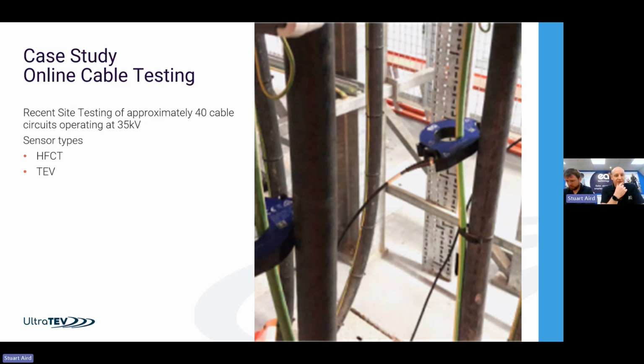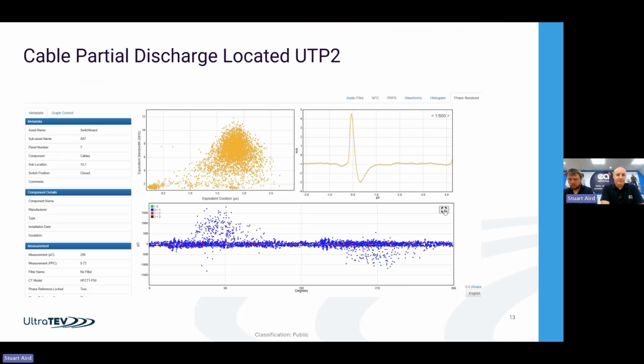A couple of the cables showed some evidence of partial discharge, which I'll go through in the next few slides. So the first one is a cable. You can see from the phase plot, we've got some clustering, 180 degrees apart, opposite polarities, and we can see possible PD. One of the features that we've added this year is being able to look at the waveform and actually map the cable from the UltraTEV Plus2 data. So we've got a short little video just showing how we do that, and I'll talk over that as we go through it.